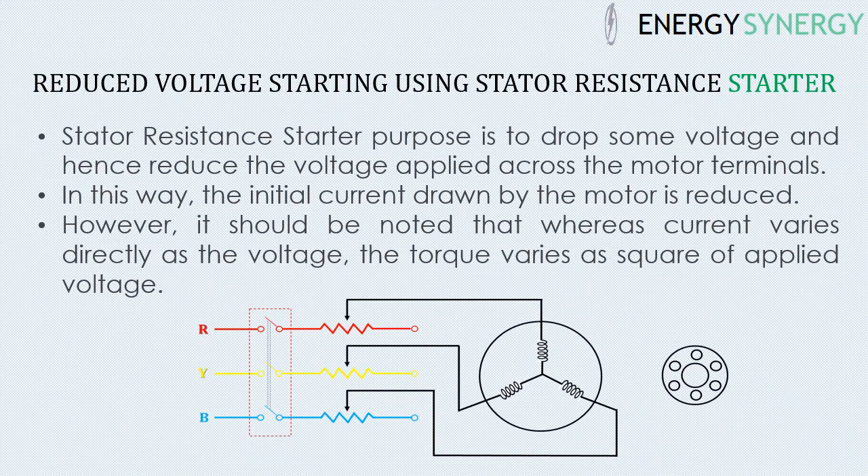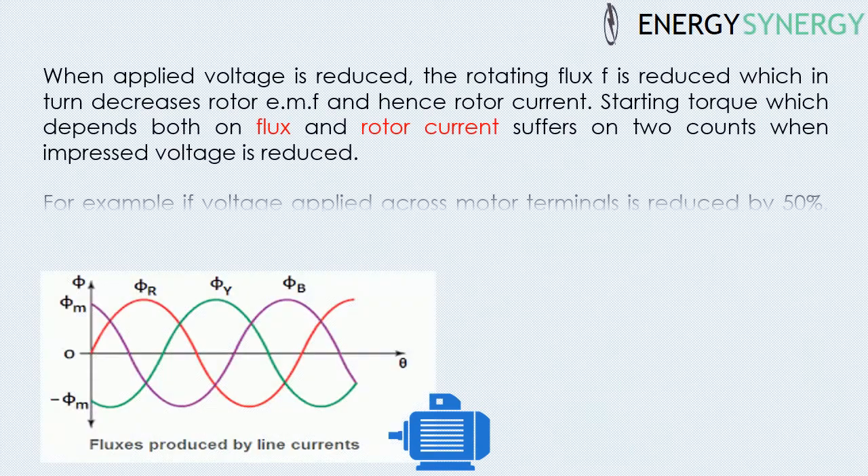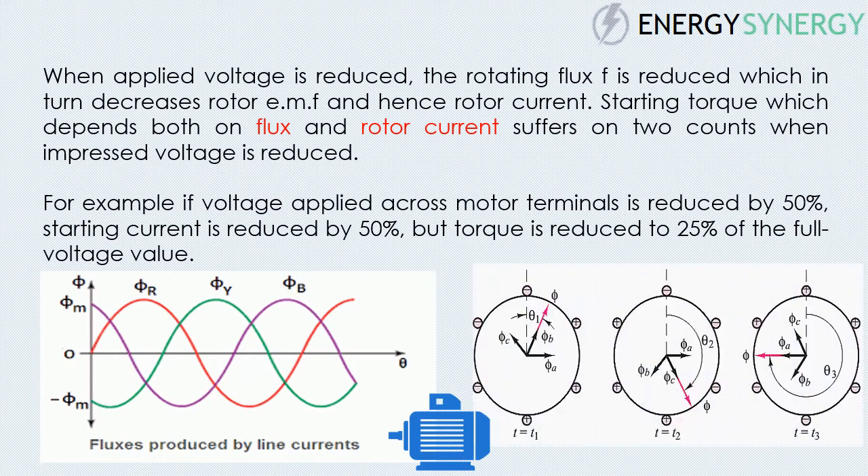It should be noted that whereas current varies directly as the voltage, torque varies as the square of applied voltage. When the applied voltage is reduced, the rotating flux is reduced, which in turn decreases the rotor e.m.f and hence rotor current. Starting torque, which depends on both flux and rotor current, suffers on two counts. For example, if voltage applied across motor terminals is reduced by 50%, starting current is reduced by 50%, but torque is reduced to 25% of the full voltage value.